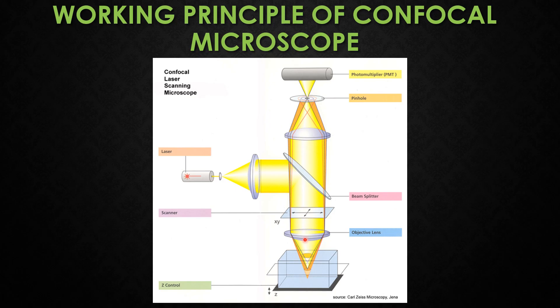The main effect of the scanning mirrors on the light is to generate a spot of light that appears stationary. A semi-transparent mirror reflects this fluorescent light away from the laser and towards the detection system. Before entering the detection system, the fluorescent light passes through a pinhole, which allows only a small central portion of the light through to the detectors.